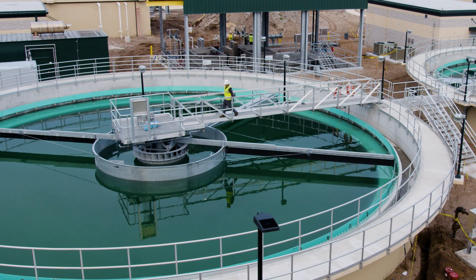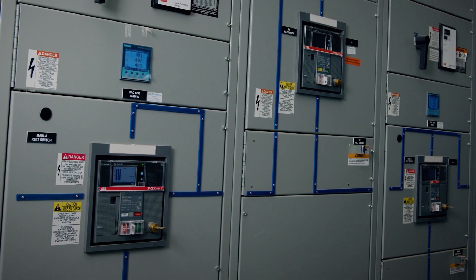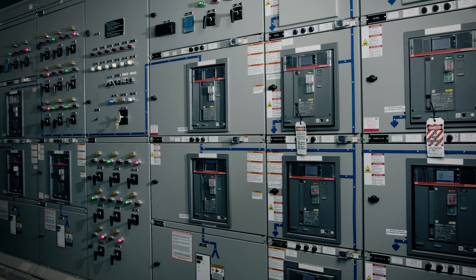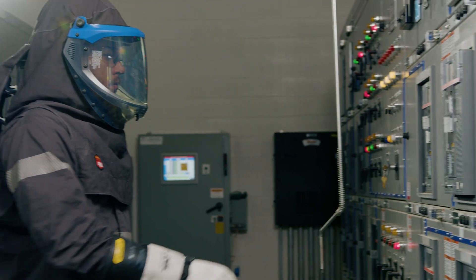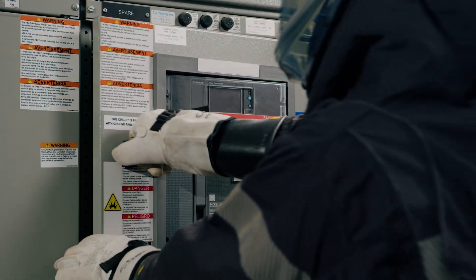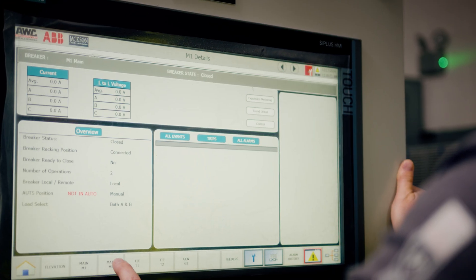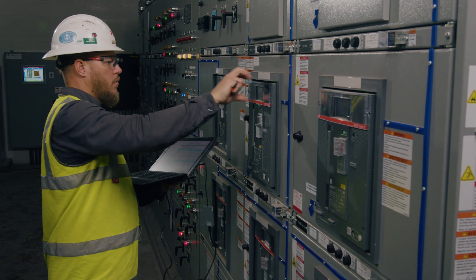The Nassau water reclamation facility contains low voltage switchgear, switchboards, panel boards, transformers, and variable frequency drives. The low voltage switchgear contains a five-breaker automatic throwover scheme so that if utility power is lost, the generator starts and breakers open and close to minimize plant downtime. The design also includes a remote HMI touchscreen that controls the automatic throwover and allows operators to open and close breakers as needed.